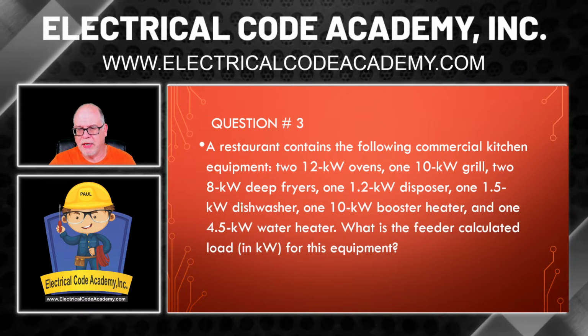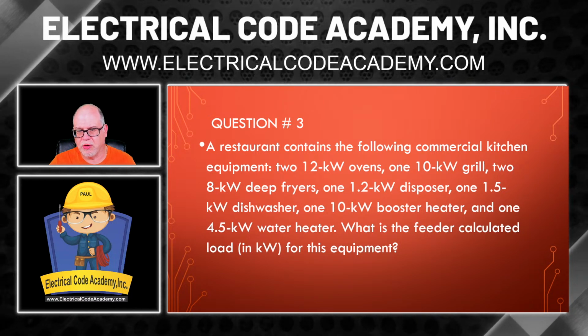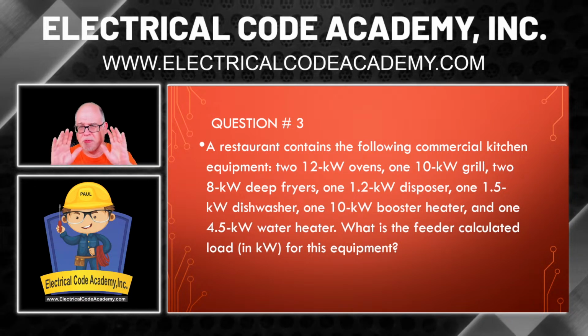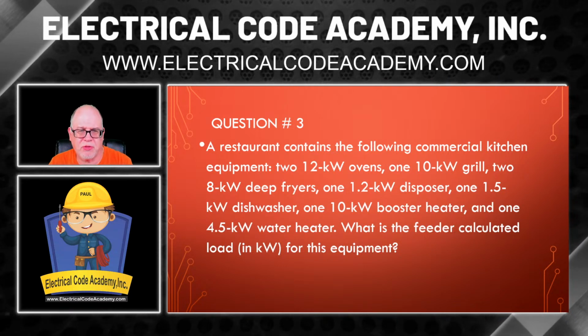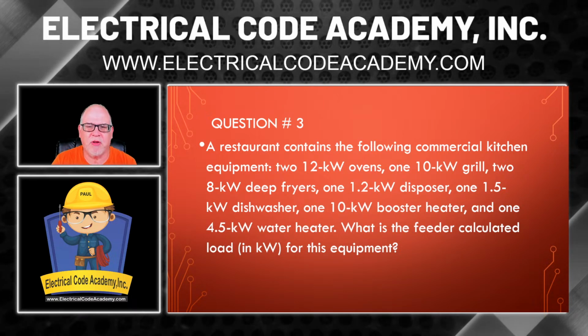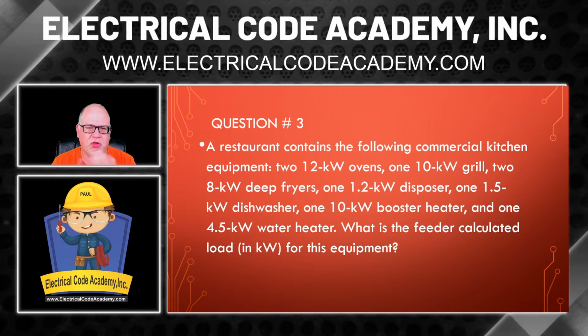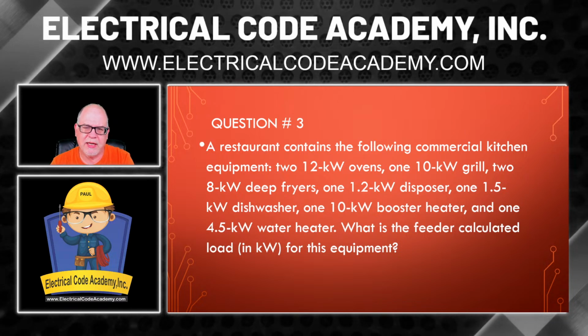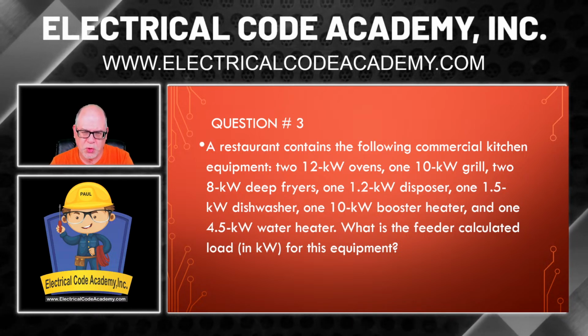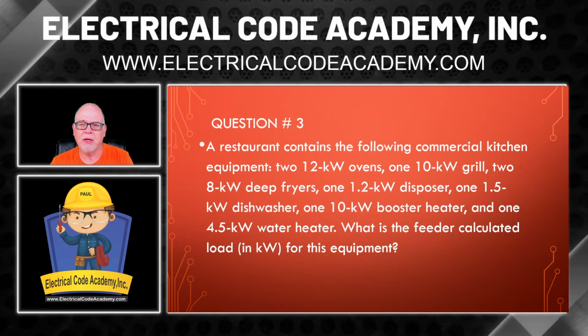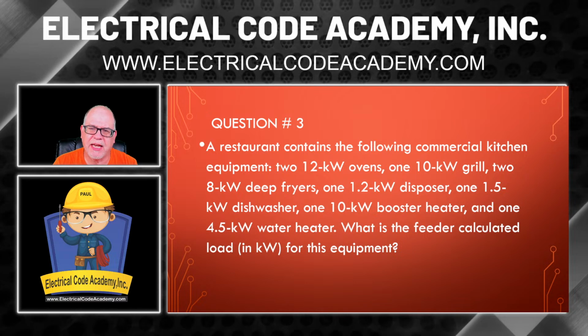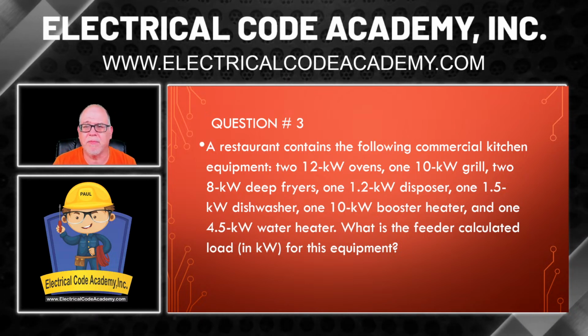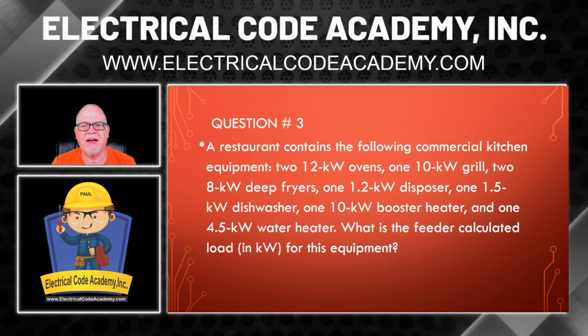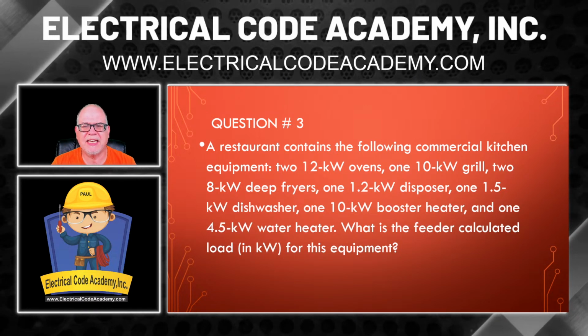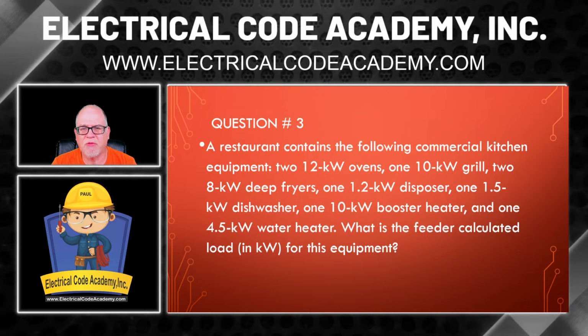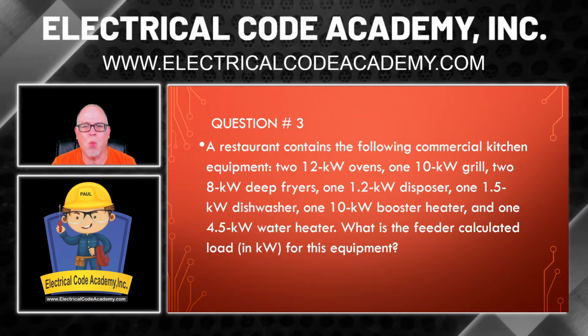All right, we're ending on a doozy now, so let's make sure you're all geared up. Remember, you can pause at any time, read this question, pause it, try to answer this question, but I'm going to walk you through it. All right, we have a restaurant that contains the following commercial kitchen equipment. There's 2 12 kW ovens. There's 1 10 kW grill. There's 2 8 kW deep fryers. There's 1 1.2 kW disposer, and I'm going to be writing all this down. I have 1 1.5 kW dishwasher. I have 1 10 kW booster heater, and we have 1 4.5 kW water heater.